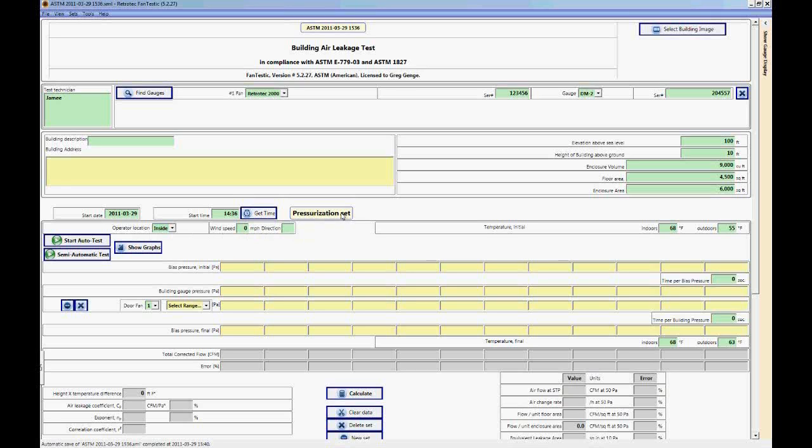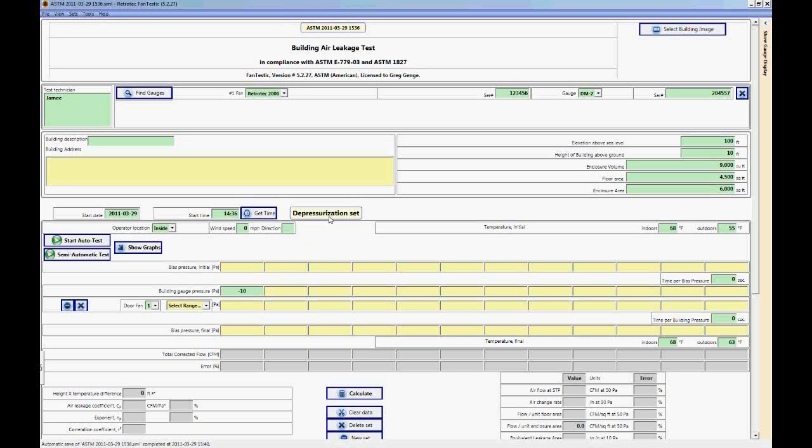Whether the set is a pressurization set or a depressurization set will depend on whether or not the operator is located inside or outside the building as well as the sign of the building gauge pressure point. For instance, if the building gauge pressure is a positive number then we have pressurized. If the building gauge is a negative number, you'll notice it switches immediately to depressurization set.